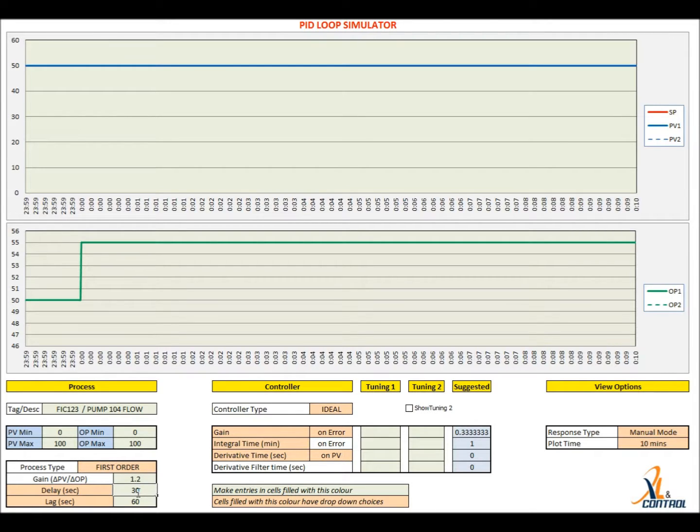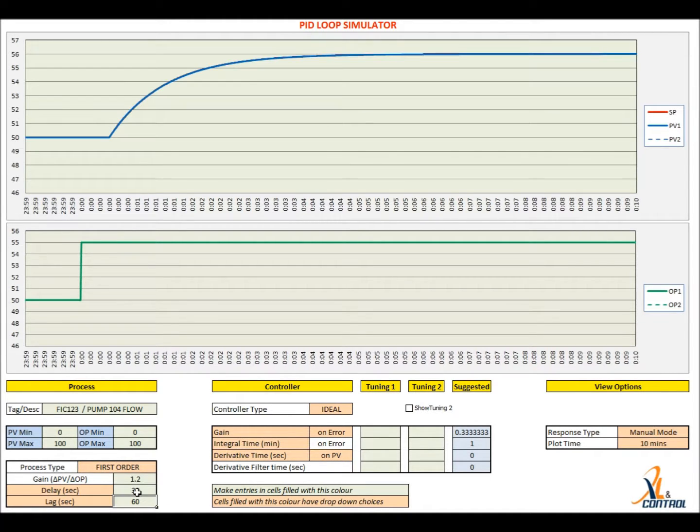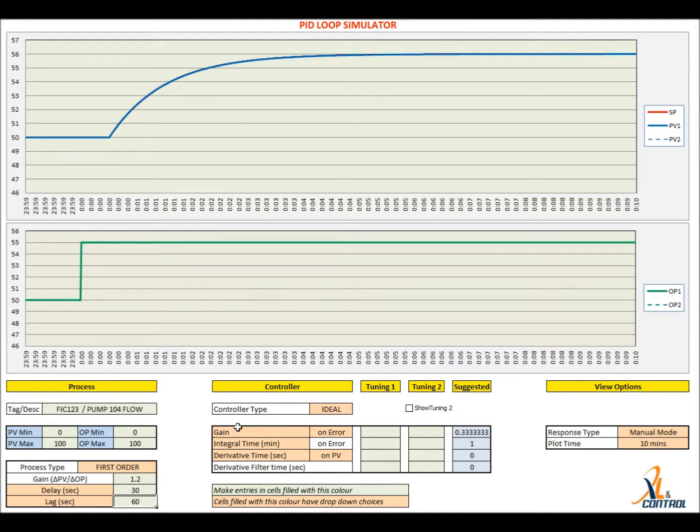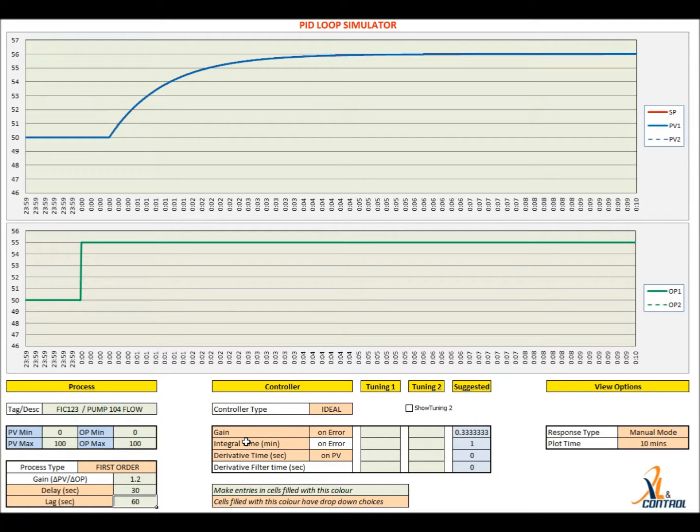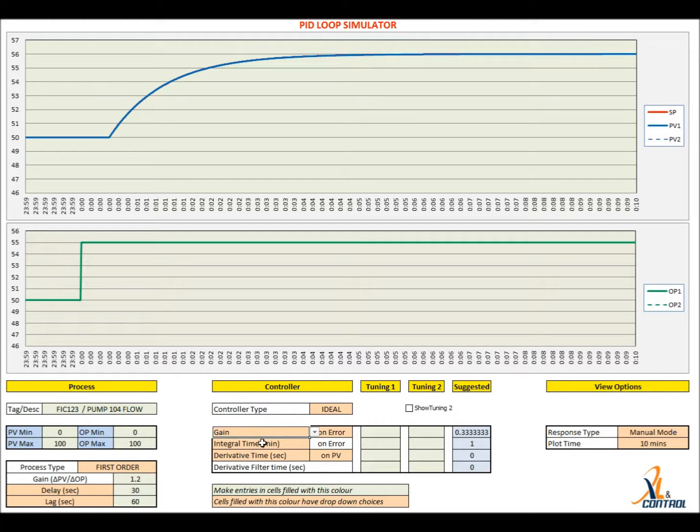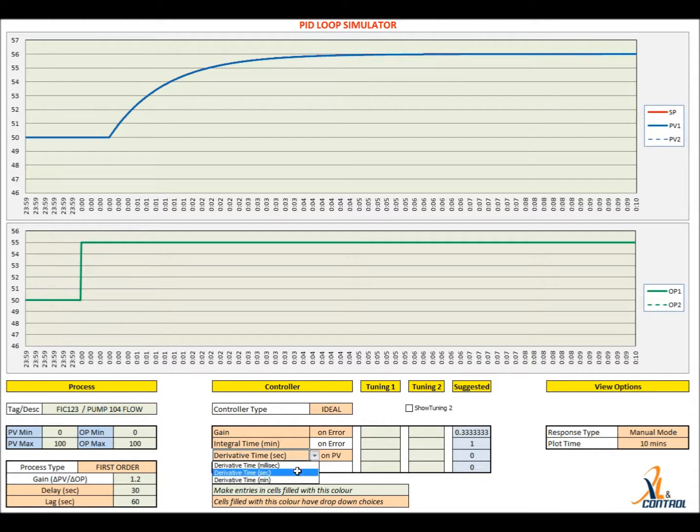Verify that the open loop response is as per the plant test. Set the controller algorithm to that used in the controller. In this illustration, we will assume that the controller used is a Honeywell DCS which uses gain. The integral and derivative times are specified in minutes. Set these options in the tool.